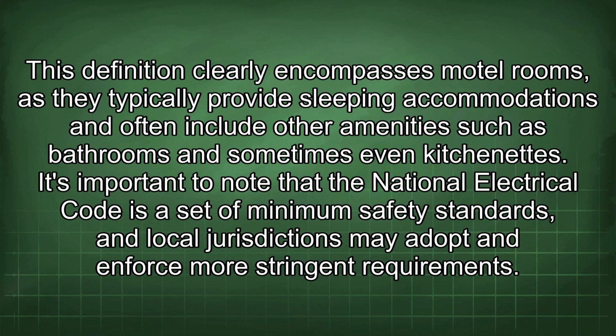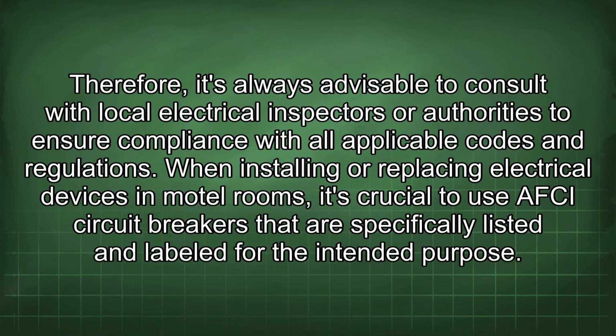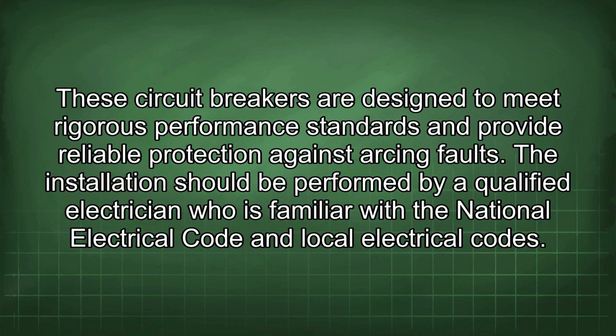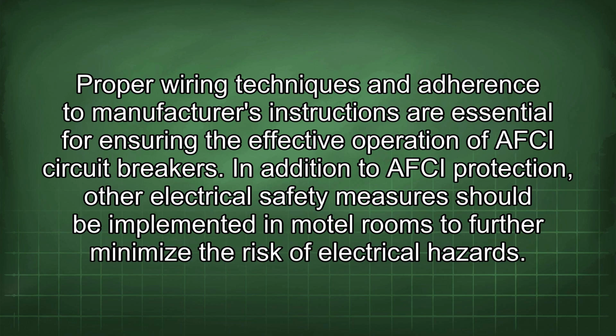and sometimes even kitchenettes. It's important to note that the National Electrical Code is a set of minimum safety standards, and local jurisdictions may adopt and enforce more stringent requirements. Therefore, it's always advisable to consult with local electrical inspectors or authorities to ensure compliance with all applicable codes and regulations. When installing or replacing electrical devices in motel rooms, it's crucial to use AFCI circuit breakers that are specifically listed and labeled for the intended purpose. These circuit breakers are designed to meet rigorous performance standards and provide reliable protection against arcing faults. The installation should be performed by a qualified electrician who is familiar with the National Electrical Code and local electrical codes. Proper wiring techniques and adherence to manufacturer's instructions are essential for ensuring the effective operation of AFCI circuit breakers.